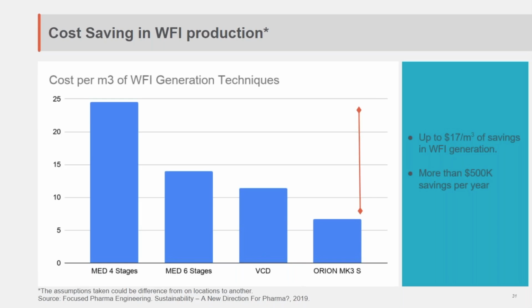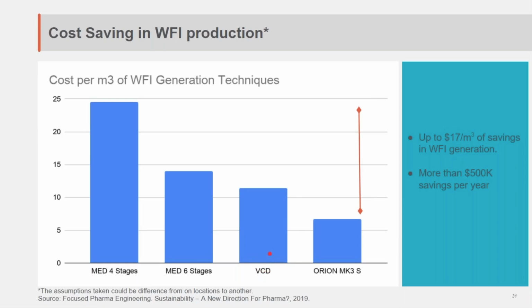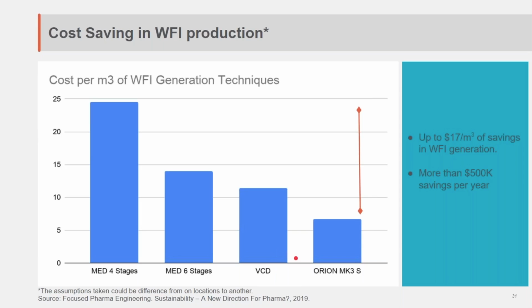So that's what those units need, and the reason you need steam is because you need the phase change from water to steam, and then you condense that to produce WFI water. So there's a lot of energy needed to take it from that phase change from water to steam. So that's where your costs are involved in that. On the VCD, it uses steam as well, but it can use 3-bar steam in conjunction with a compressor on the unit, which uses quite a lot of electricity, to be fair. That's where your utility costs are on a VCD.